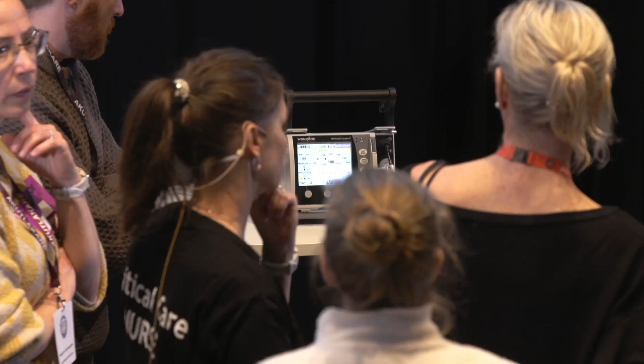Now, the reason that you've got that different mode is the ventilator software is looking at the curve underneath the flow. All right, and so it's looking at the shape of the curve as you're pushing down. And that shape of that curve is really, really important. It's interpreting hands, which are very different to a machine, because a machine has a very square shape to the flow curve as it's pumping down.